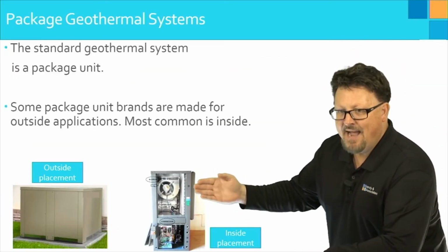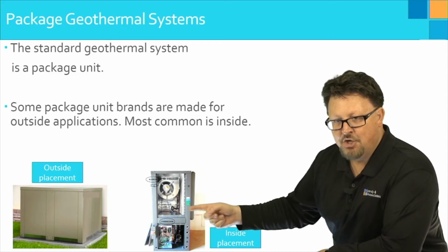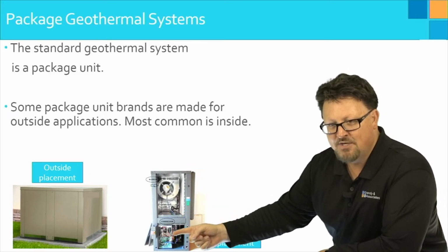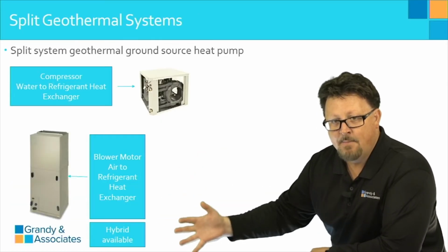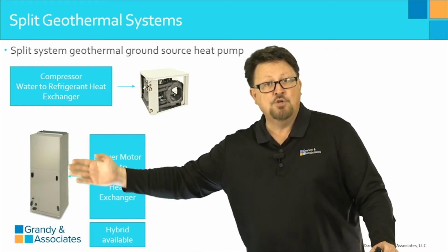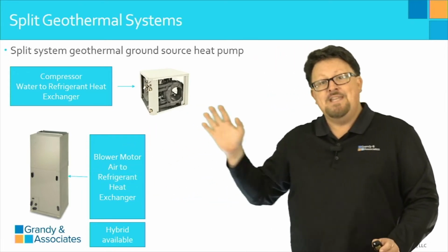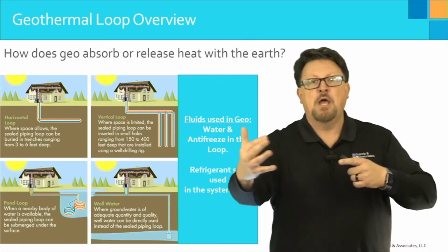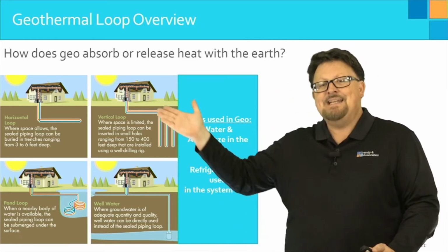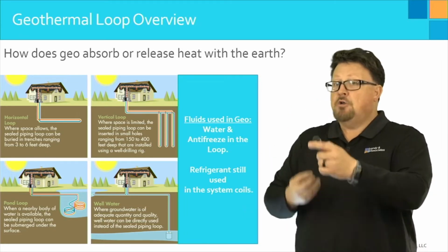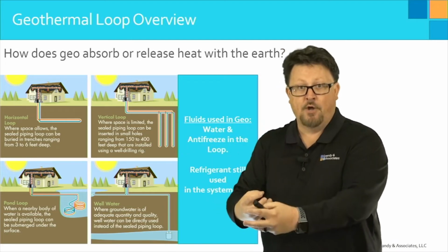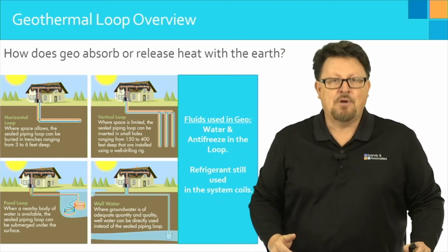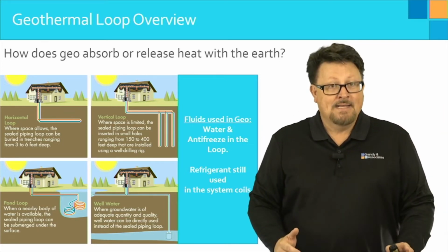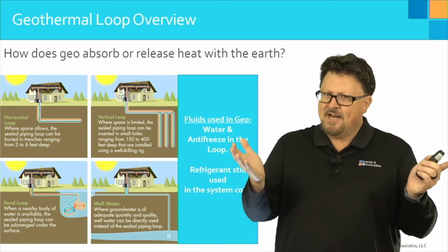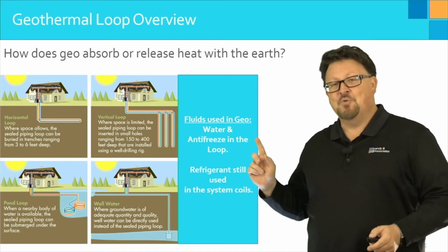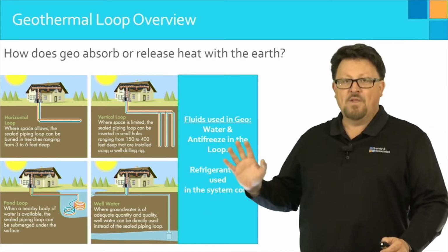Let's back up. In our geothermal package unit, you have a coil made in this section, plus a smaller coil down here. In our combination setup, inside the geo-approved air handler, there's a coil as well. So yes, the water solution moving through the ground is part of the heat exchange of geothermal, but the product itself also has refrigerant running through the system coils, aiding in that heat transfer. Keep that in mind in case it shows up in a review or quiz question, since this can be a little confusing.